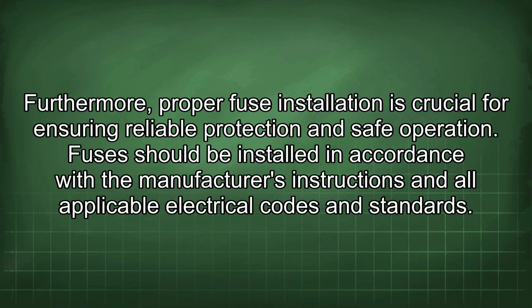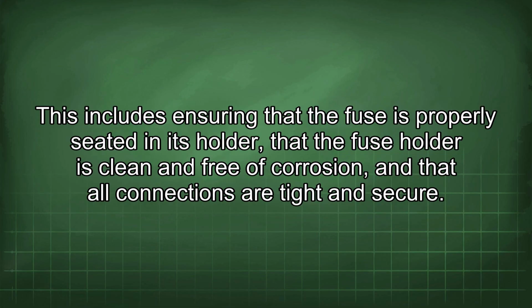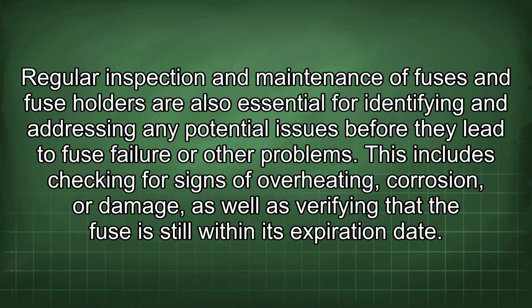Fuses should be installed in accordance with the manufacturer's instructions and all applicable electrical codes and standards. This includes ensuring that the fuse is properly seated in its holder, that the fuse holder is clean and free of corrosion, and that all connections are tight and secure. Regular inspection and maintenance of fuses and fuse holders are also essential for identifying and addressing any potential issues before they lead to fuse failure or other problems.